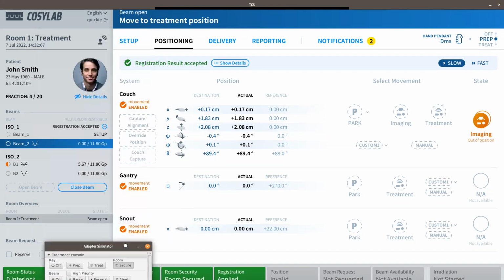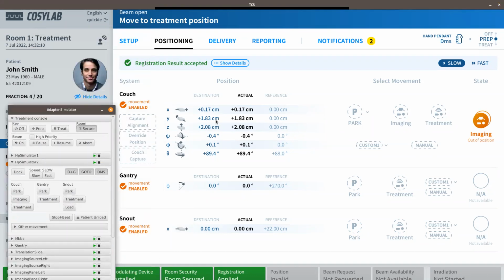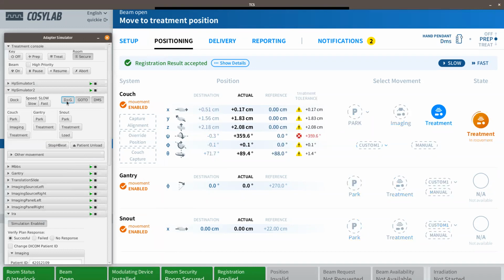The next instruction is move to the treatment position. Now we will move all three subsystems that can be moved into the treatment position. So I will select treatment position for the couch. Now the patient couch is in the treatment position. The next step is to move the gantry. This is rotating the beamline through the room. I select treatment position and perform the movement with the hand pendant. And now the gantry is also in the treatment position.